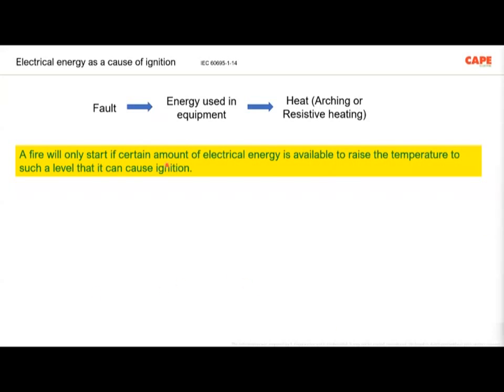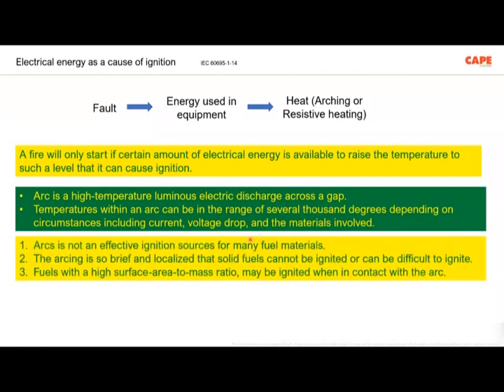Thank you, sir. So now, electrical energy causing fire. The IEC 60695. One misinterpretation which I wanted to tell you about is arc: whether an arc can ignite fire. An arc is a high temperature luminous electrical discharge across a gap. The temperature within the arc can go to several thousands of degrees, but an arc is not an effective ignition source for many fuel materials. Even solid combustible materials cannot be ignited by an arc because it lasts for a very short time.